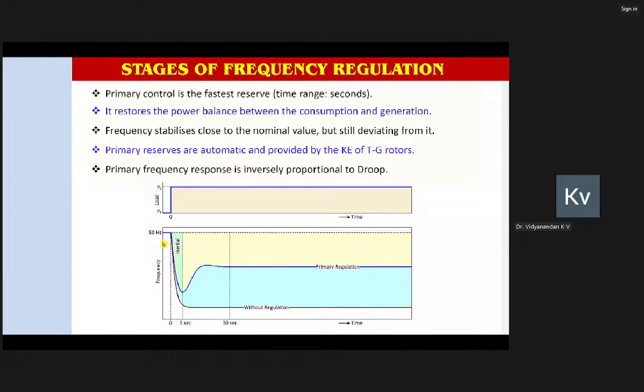Please note that frequency is constant, speed is constant, but it is not the nominal value, because our original value was 50 hertz. Now with the primary controller, you will never be able to restore the frequency back to the nominal value, and that is why we need the integral action through the secondary control. Your load controller is basically the secondary control, in which an integrator is provided.